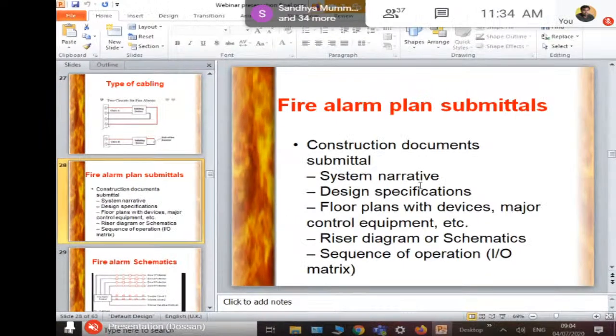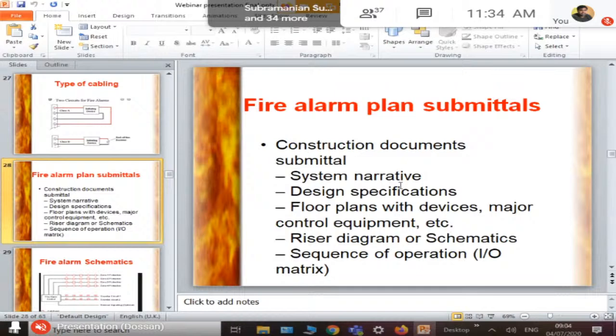Like you have fire alarm panels, you have repeater panels, you have the mimic panels here and there, you have a number of smoke detectors, you have a number of devices. You should have major floor plans and how many equipment we have connected to this, and the design specification on what basis the standards are being followed. Again, we'll have two more important documents, called a riser diagram or schematics, and a sequence of operation matrix. I'll show you a couple of small slides showing what is a riser diagram and what is a sequence of operation matrix. This is how a fire alarm single line diagram looks like.